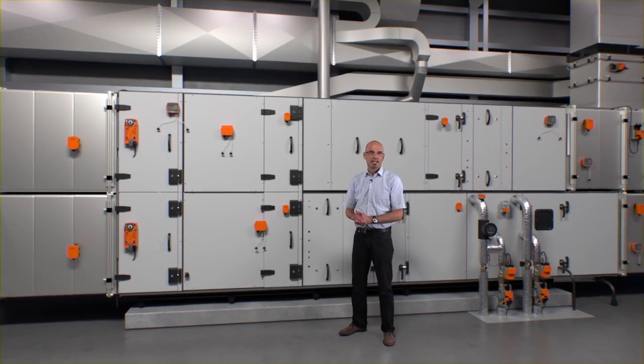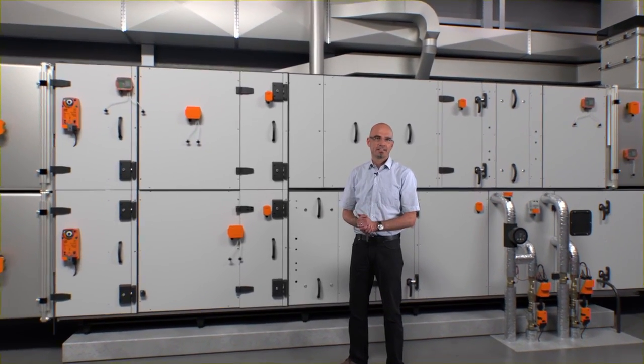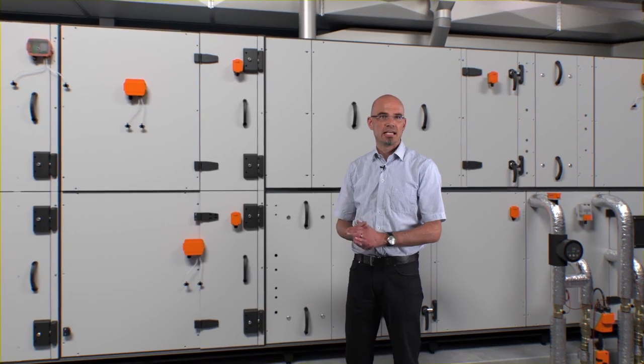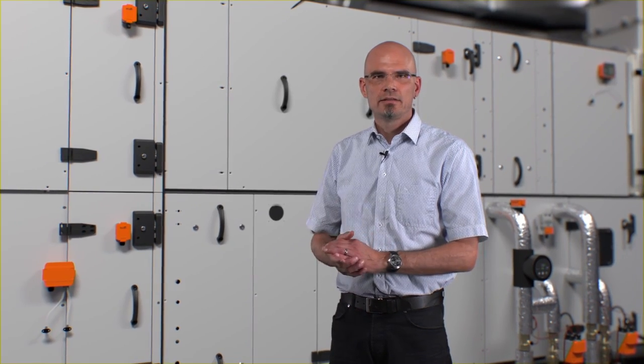Here we are in a technical room in the basement of this building. Behind me you can see a centralized air handling unit designed as an air conditioning system. This unit has the task of intaking fresh outdoor air, conditioning it regarding temperature and humidity, supplying it to the rooms of the building and removing the used air. The ventilation rate and the required level of temperature and humidity are based on an overall heating and ventilation concept.